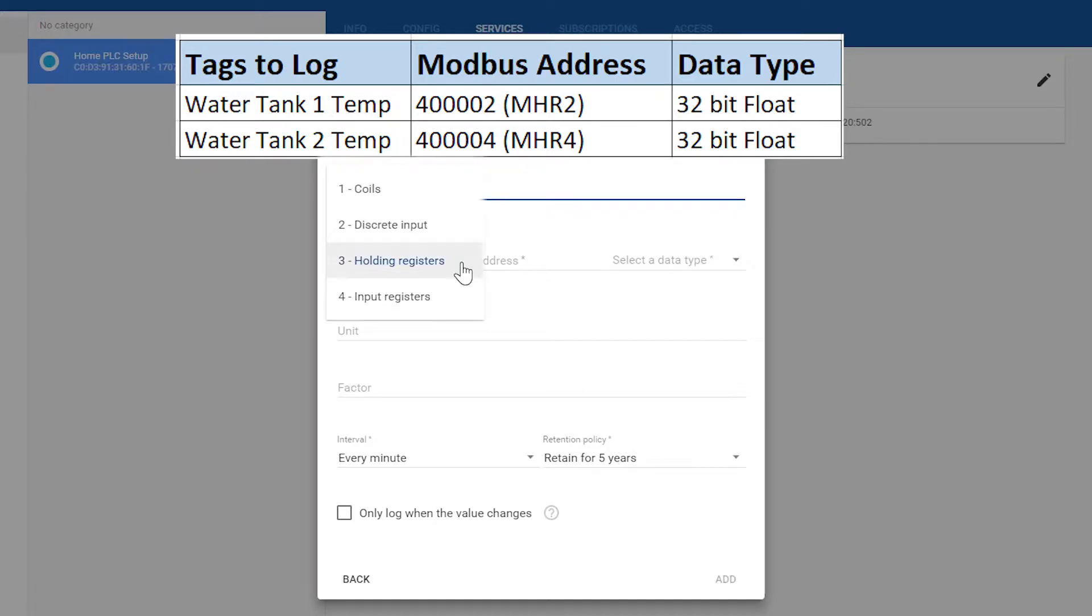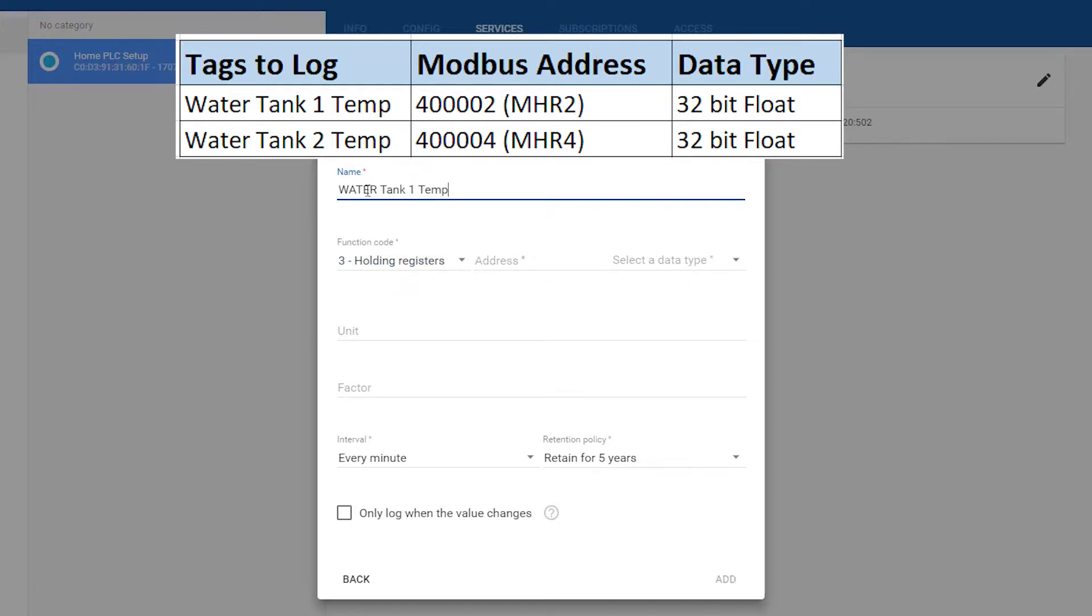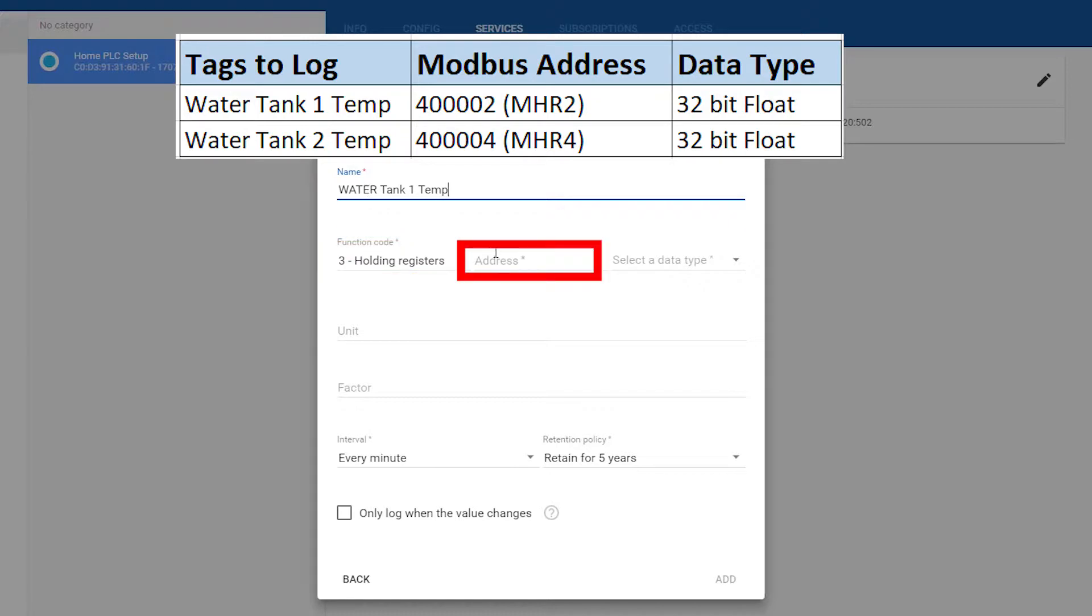With the logger, you will be able to address coils, discrete inputs, holding registers, and input registers. Since these tags are in the 400000 range, that means they are holding registers. And since we are defining that they are holding registers here, all we need to do is place the offset address here.